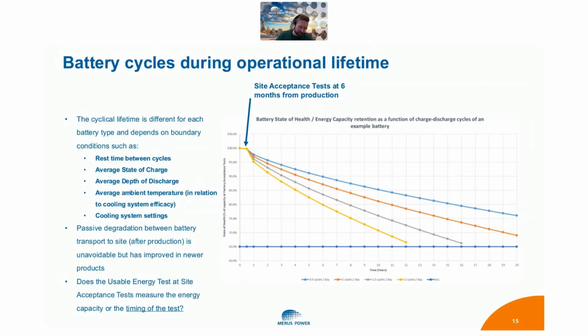So what affects this degradation and cycling: rest time between cycles, average state of charge during cycling, average depth of discharge, average ambient temperature, and cooling system settings for the battery. Therefore, if you are thinking of the difference between forecasted performance and the actual performance of the equipment, you understand how simplified it is to talk about 1 cycle a day, 2 cycles a day, and then base guarantees on that.